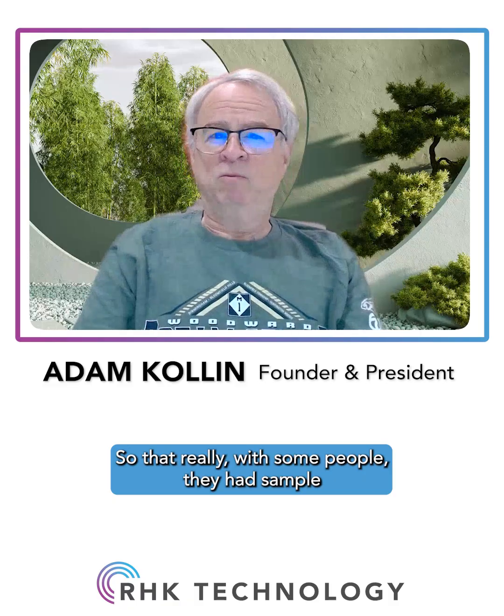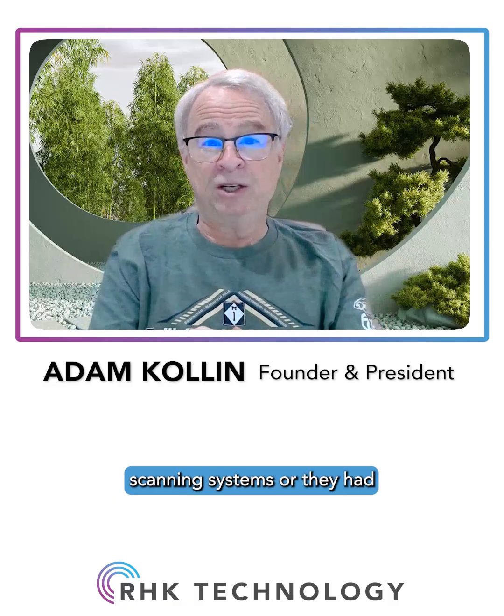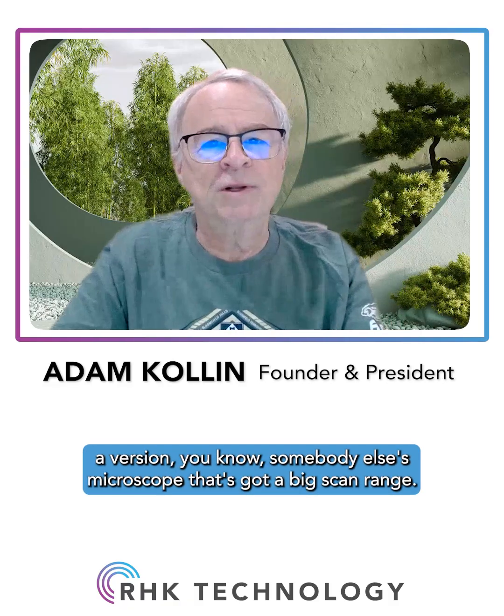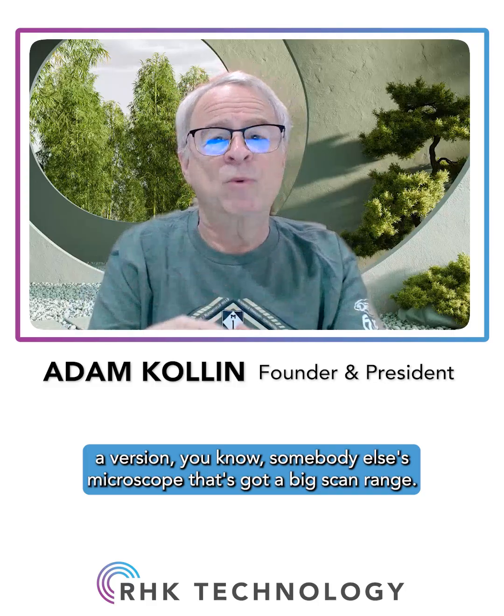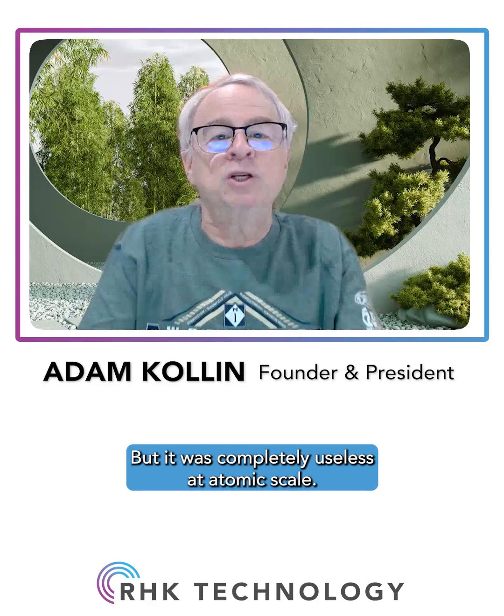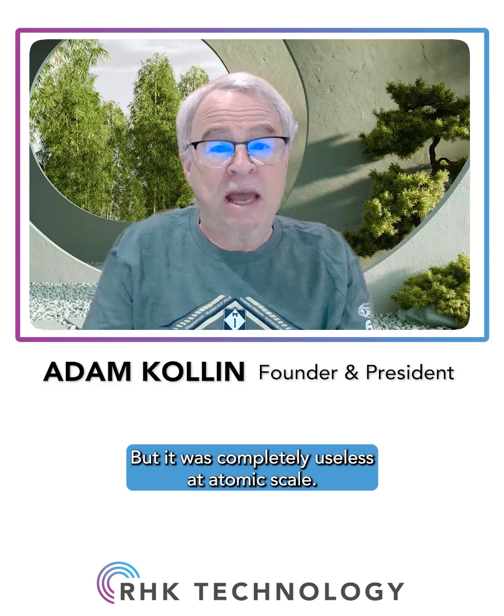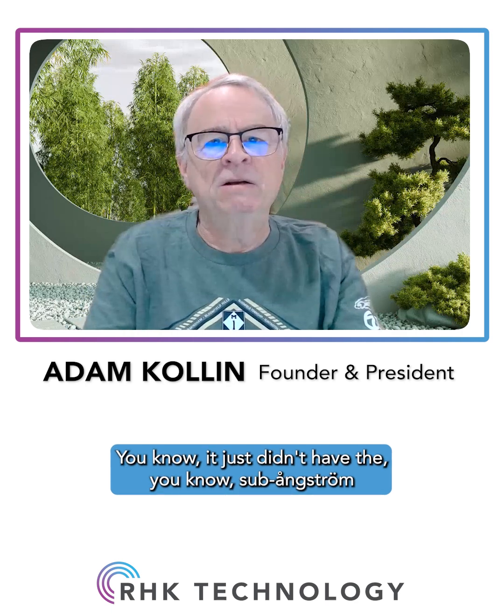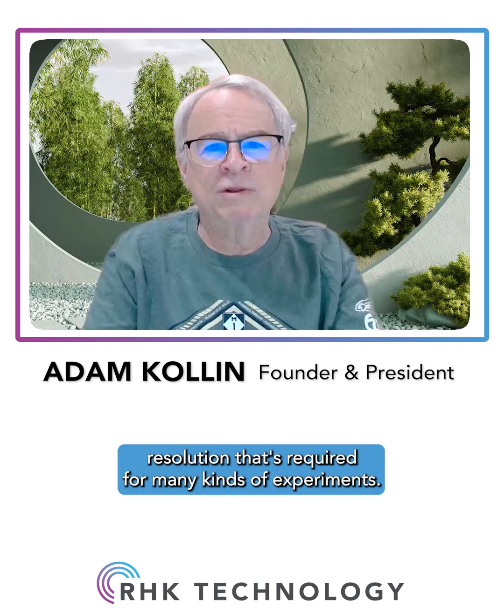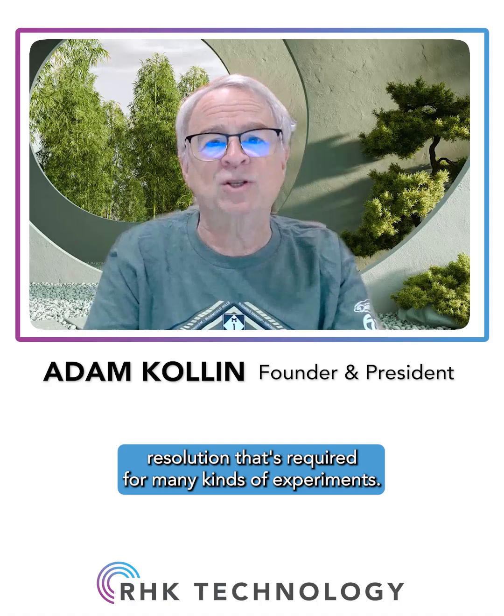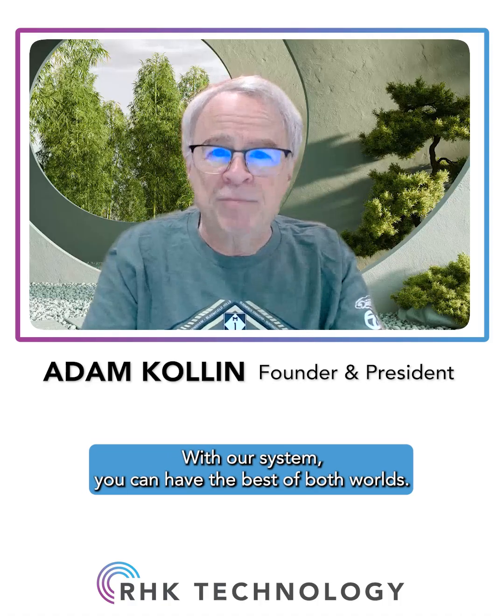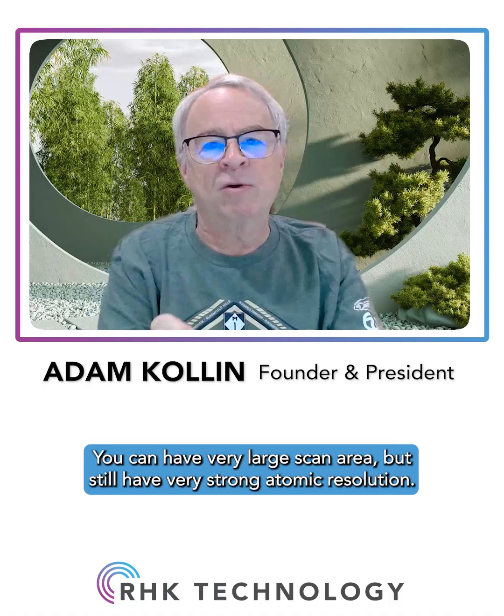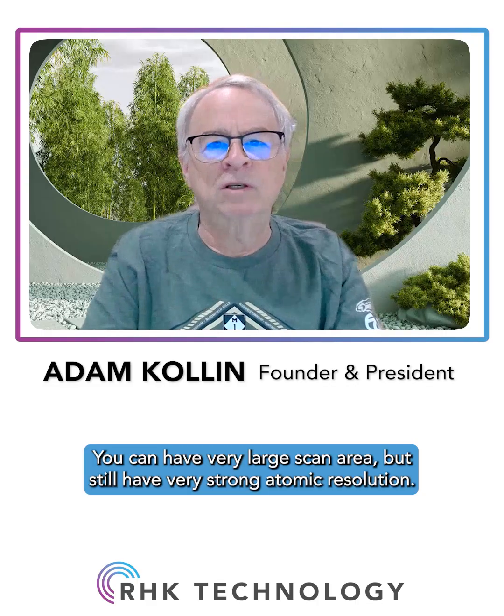So that really, with some people, they had sample scanning systems, or they had a version, somebody else's microscope that's got a big scan range, but it was completely useless at atomic scale. It just didn't have the sub-angstrom resolution that's required for many kinds of experiments. With our system, you can have the best of both worlds. You can have very large scan area, but still have very strong atomic resolution.